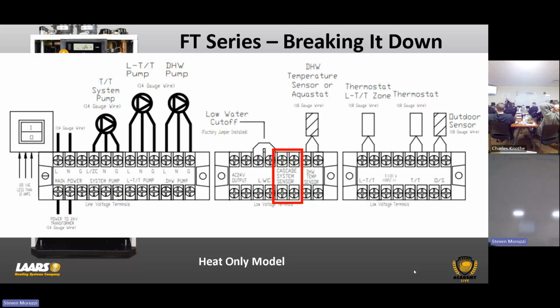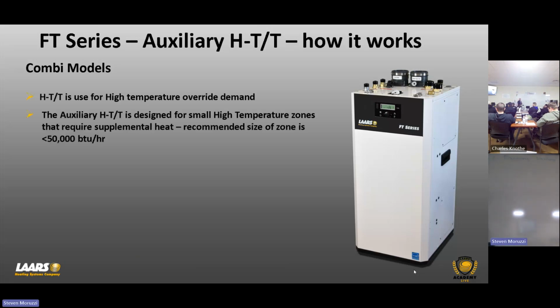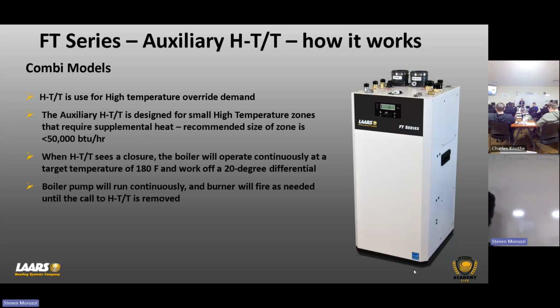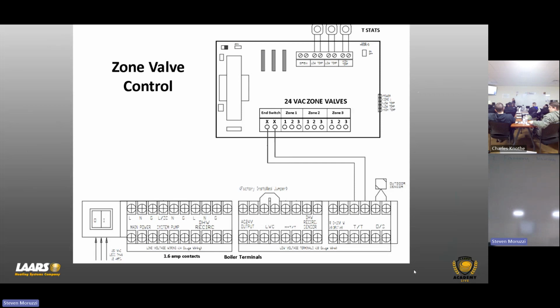Because they weren't using it. It wasn't working correctly as a secondary high temperature zone, and it was originally designed just for the holidays, where you can't turn the boiler on and off. So that's a double feature. After 100 hours of constant on, it times itself out. It's back to normal operation. So like he's saying, like at a Florida room or front porch, you have to do it off of regular TT off your zone panel. And that HTT was really designed for small zones, 50,000 BTUs or less. So I need to update this. It did come out last week, and I apologize.